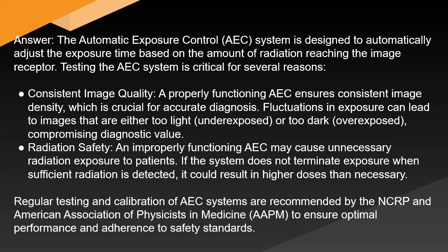If the system does not terminate exposure when sufficient radiation is detected, it could result in higher doses than necessary. Regular testing and calibration of AEC systems are recommended by the NCRP and the American Association of Physicists in Medicine (AAPM) to ensure optimal performance and adherence to safety standards.